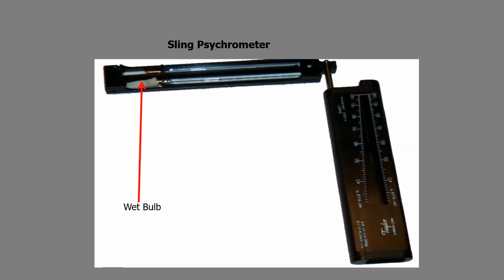This is sort of an old school non-digital psychrometer. You've got two thermometers in here, if you will. You have a dry bulb one and you have a wet bulb one. And there's a little cotton sock here and a water reservoir here. The sock wicks up the water and gets a wet cotton sock. And what the user of it would do would be to spin it around, and as you spin it around, water evaporates off that wet cotton sock. The drier it is, the more evaporation occurs, the lower that wet bulb will be. The wetter it is, the opposite occurs.